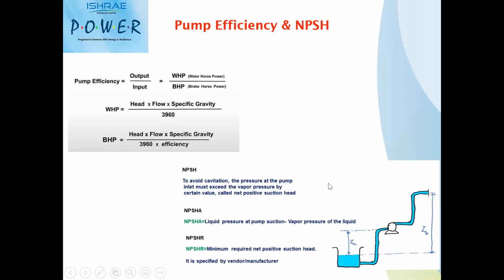If you have the sump level on the higher side, that is above the pump eye of the impeller, you have to add that height, whatever height is generated due to the water column. So atmospheric pressure plus the height of the liquid above the pump eye level minus the frictional losses on the pipe side will give you the net positive suction head available at the site. And please note that your NPSH available should always be greater than NPSH required by the pump to have a smoother operation of the pump.